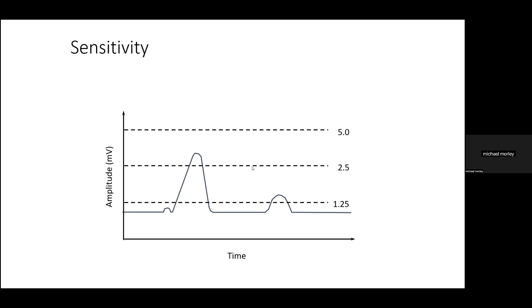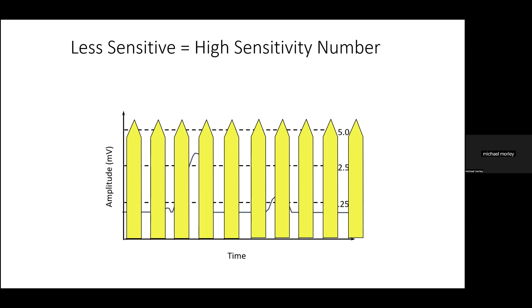If you turn the knob to a higher millivolts, so a higher number, then you're setting the fence higher. You're saying that the pacemaker system should only take notice of any signals which are above 5 millivolts. But in this case, that means that we're not going to see any intrinsic activity.